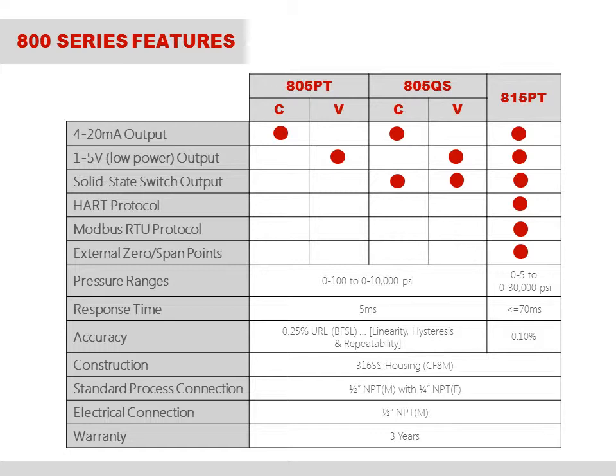Note that only the 815 and the 805 QS provide a switch output. Both switches are a single pole, single throw, normally open, solid state relay that is rated 30 volts DC and 120 milliamps. One significant difference is that the switch output of the 815 can be configured 9 ways, whereas the switch on the 805 QS has only 3 configurations.